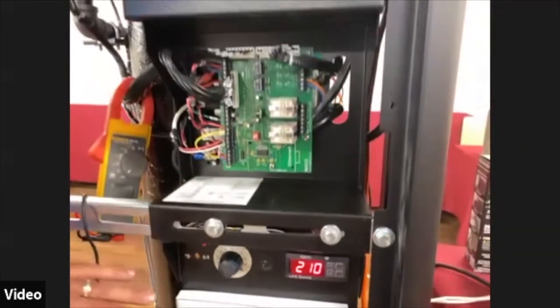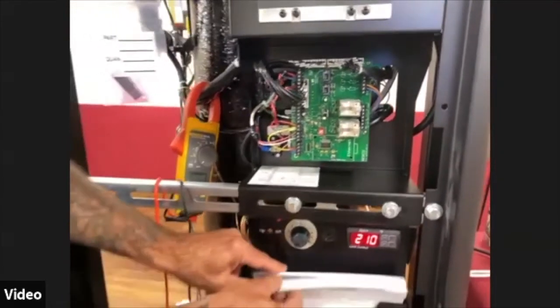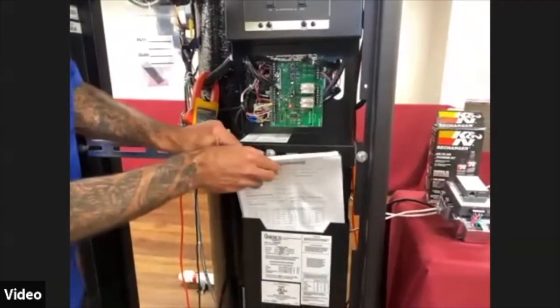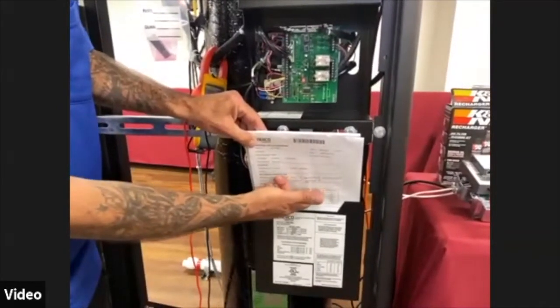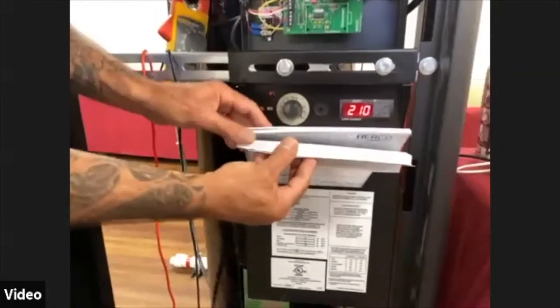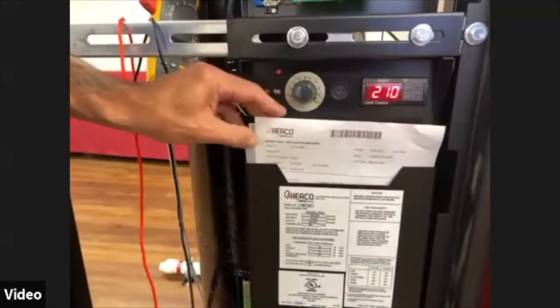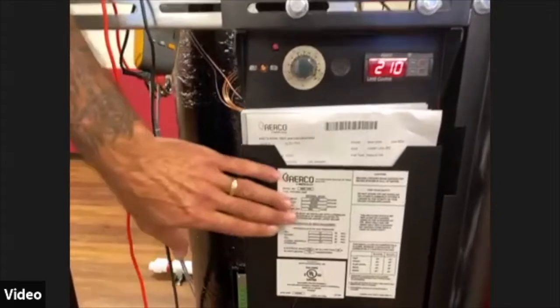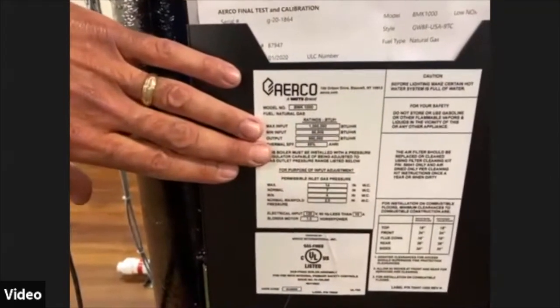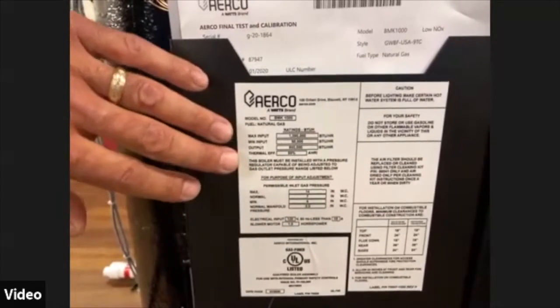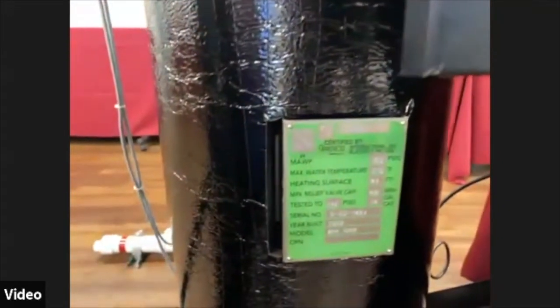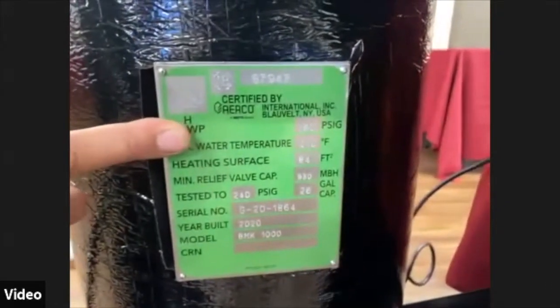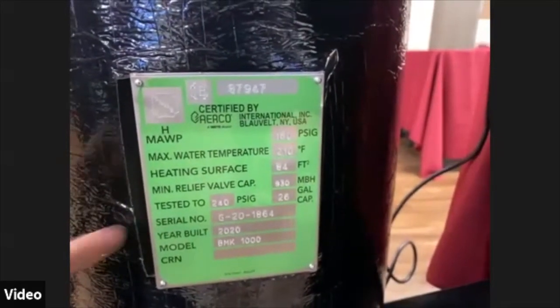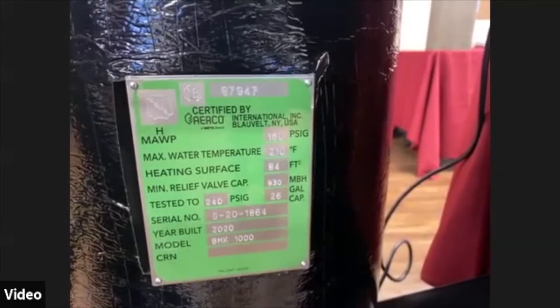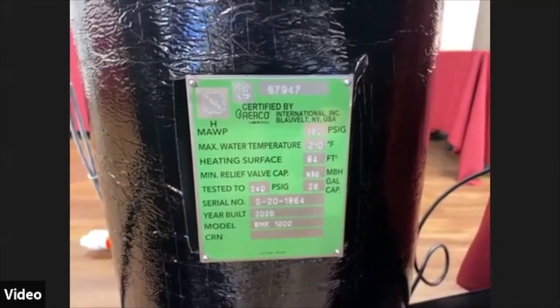In addition to that, in the front of here too, they also give you this nice little compartment here for the I/O manual and the combustion calibrations that they did at the factory. So everything is in here that you need. I recommend leaving it in here for reference for the future. And all of your pertinent information will be located on the sticker just below that. Model, serial numbers, BTU ratings. And in addition, there's also the tag on the boiler heat exchanger. So this is your H stamp tag, as well as your model, serial number, maximum allowable water temperature, maximum allowable pressure.